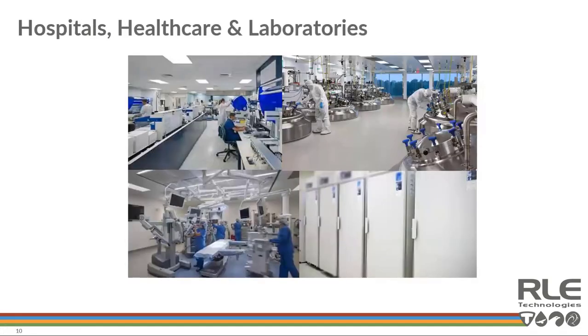When it comes to hospitals, healthcare, and laboratories, there's more on the line than just protecting assets. In these cases, sometimes even lives can be at risk. I worked with a healthcare provider that contacted me, as usual, in a panic after the damage was already done. They had been pulling summary alarms from their generator, but weren't pulling detailed information that might be available via a protocol like SNMP, Modbus, or BACnet. What ended up happening was their block heater on the generator got stuck in the on position. They ran into a situation where they had to transfer the load to the generator, but as soon as they transferred the load over, the generator went into alarm and an immediate shutdown, and the entire facility went black.